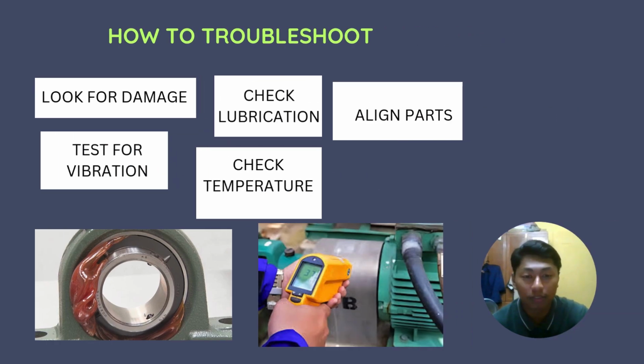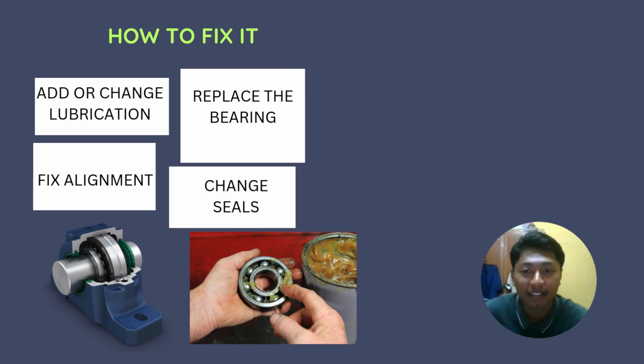Okay, next is how to troubleshoot bearing failure. Firstly, look for the damage, then check the lubrication, test for vibration, and check the temperature. Lastly is align parts. Other than that, how to fix the bearing failure? First is add or change the lubrication. Second is replace the bearing. Third is fix alignment. And lastly is change the seals.